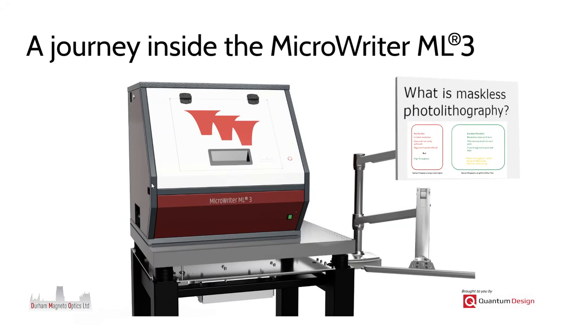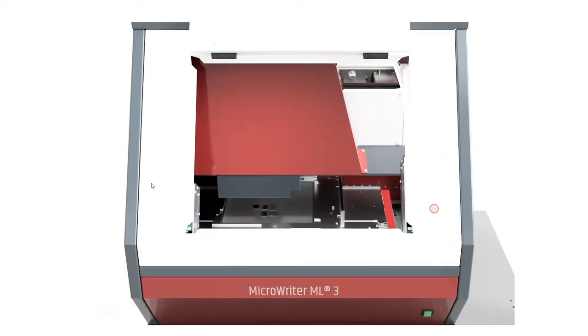So now let's open the front door and let's look at what's under the bonnet. The machine has a modular conception where each module can easily be disconnected from the rest of the system, which makes diagnostics and repairs very easy. Modules include optics units, interferometer, XY stage, control electronics, and so on. The optics is hidden behind the red cover, which prevents the user from ever being at risk of seeing the high power UV light.